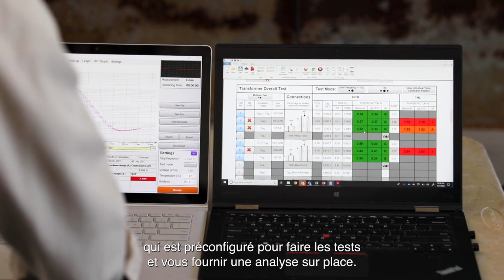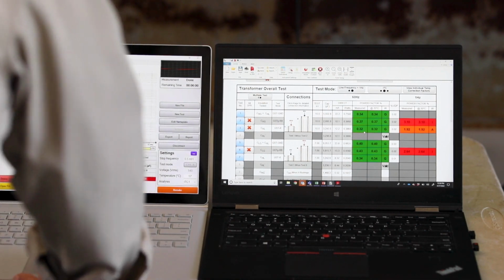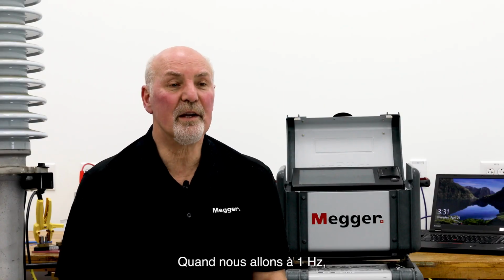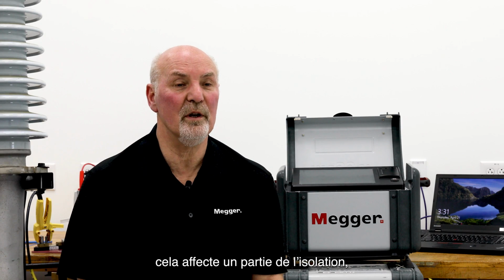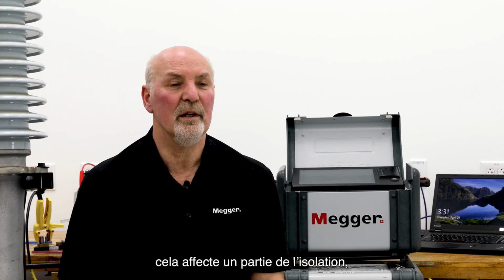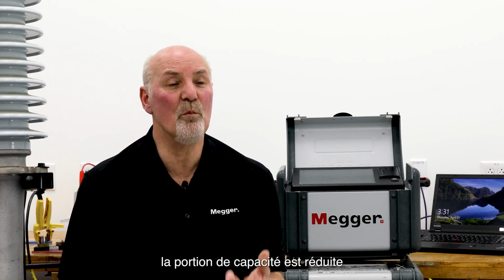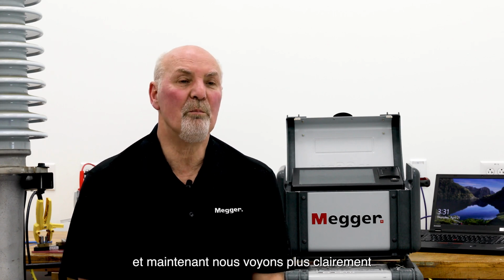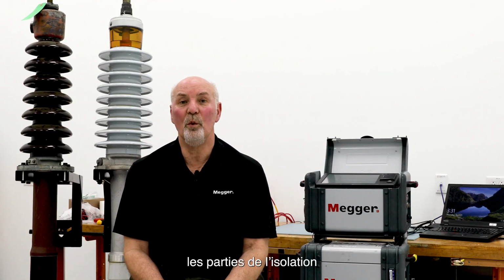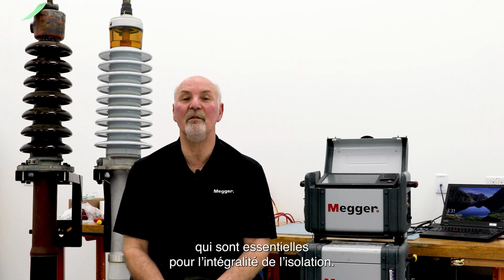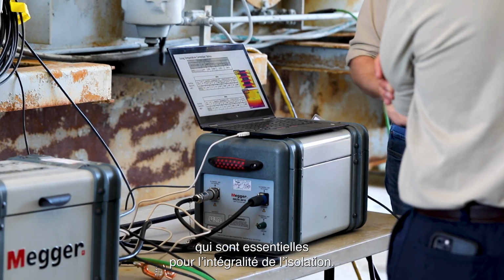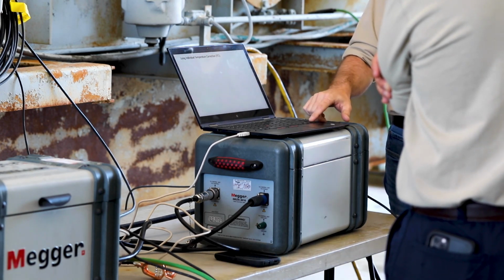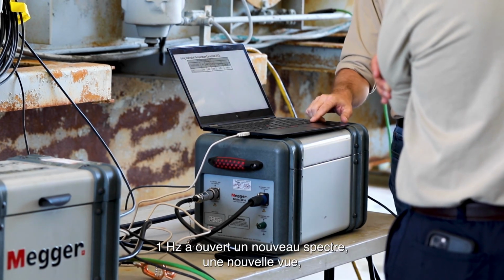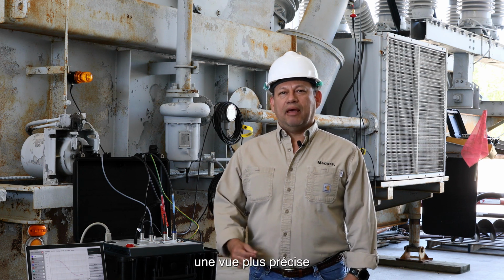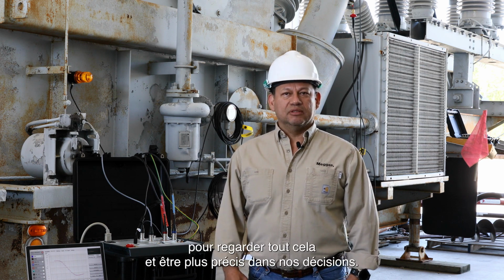When we go to 1 Hz, that effect of one part of the insulation, the capacitive portion, is reduced, and now we see more clearly the parts of the insulation which are critical for the integrity of insulation. 1 Hertz has opened a new spectrum, a new view, a more sensitive view to look at this and be more accurate on our decisions.